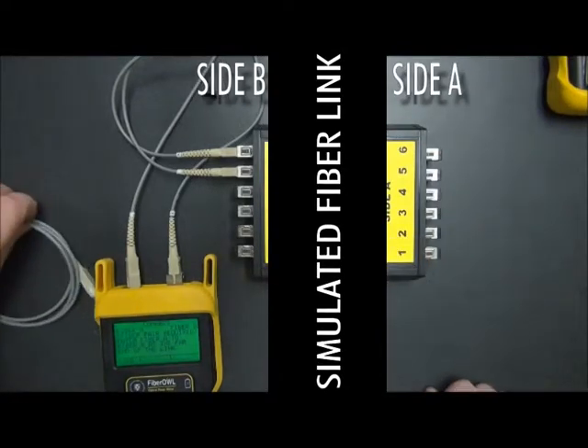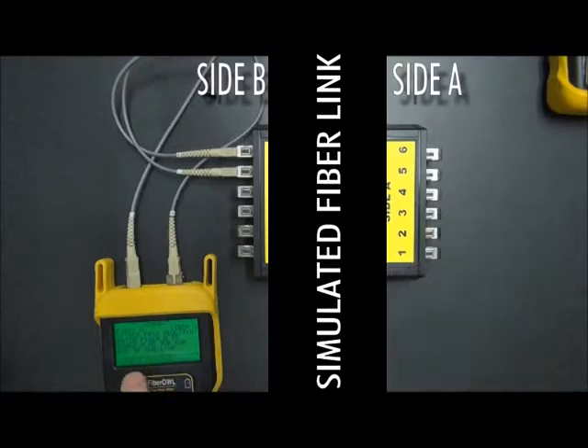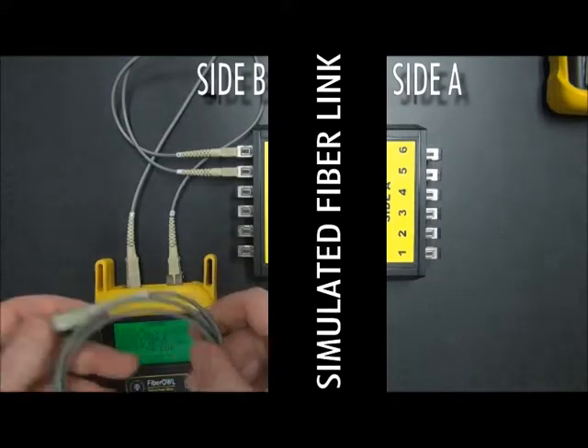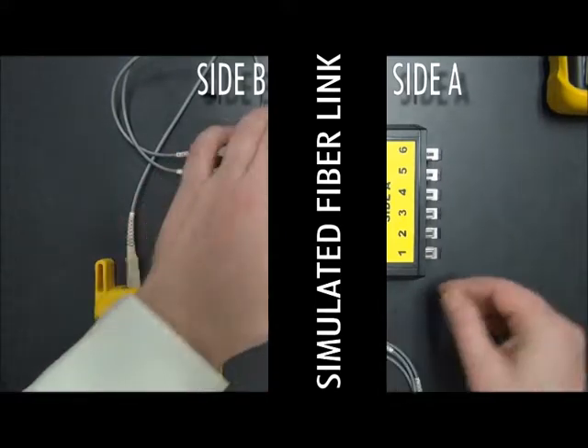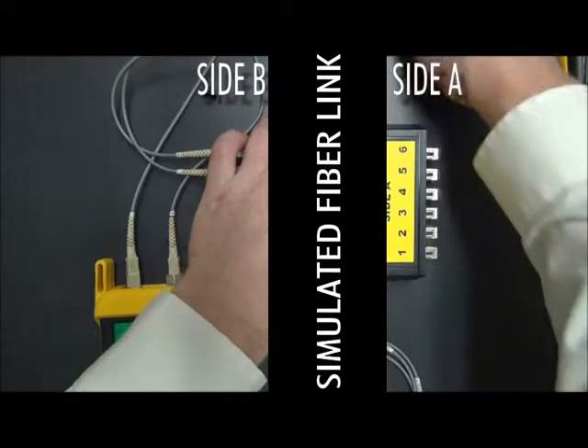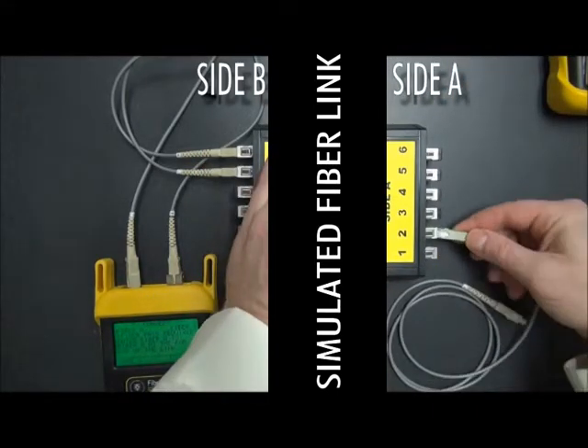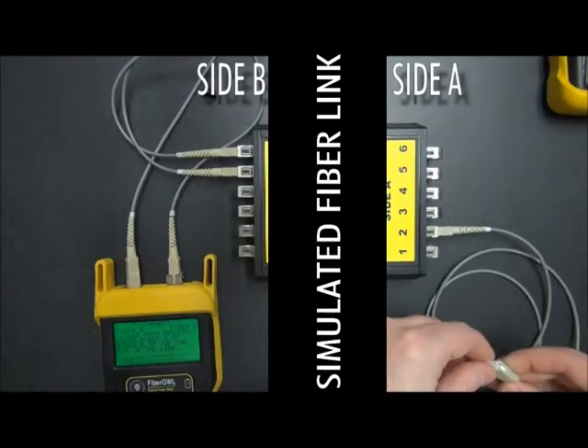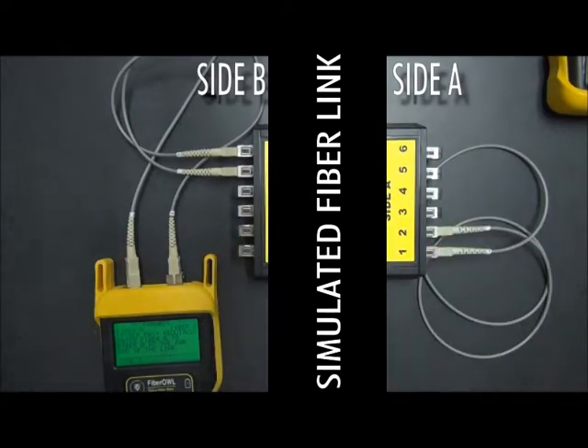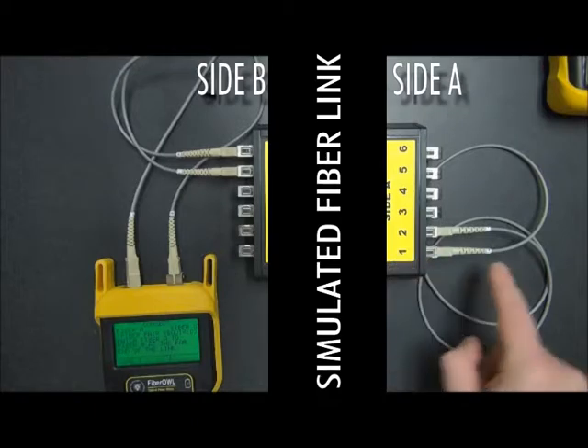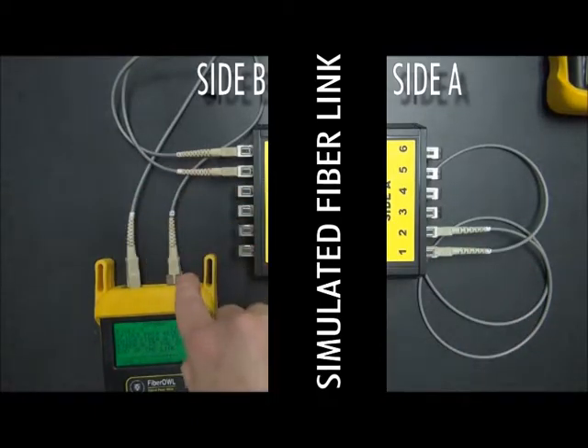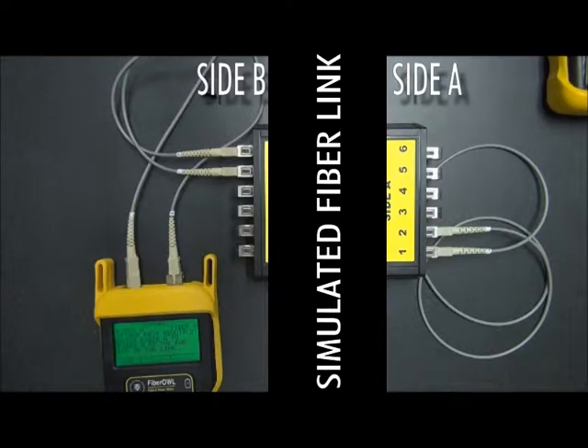But at the far end, obviously we need to have a loop back. That's what this says here, patch fiber A to fiber B at the far end of the link. So we take our 3rd patch cable and we connect it to ports 1 and 2 on the other side. Okay, now as you can see, we have a loop. It goes from fiber 1 all the way through the loop into fiber 2 here, comes around this loop and comes back on the receive fiber into this port here. So once we've connected in, we simply press F1 for done.